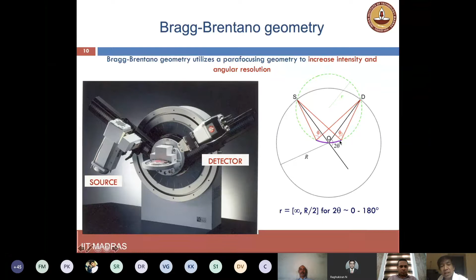If you do not keep the sample exactly at the center of the goniometer circle, then you will have errors. I'm not going to discuss the errors, but I would like to highlight that this is what is called Bragg-Brentano geometry, in which the sample is kept at the center of the goniometer, which helps in parafocusing geometry. This geometry requires the sample to be curved, but in reality that is not possible. You always have a flat sample that you place on the stage, and that also leads to error, which I'm not going to focus on today. All I'm trying to highlight is that in any powder diffractometer, we follow Bragg-Brentano geometry and get the diffraction signals.